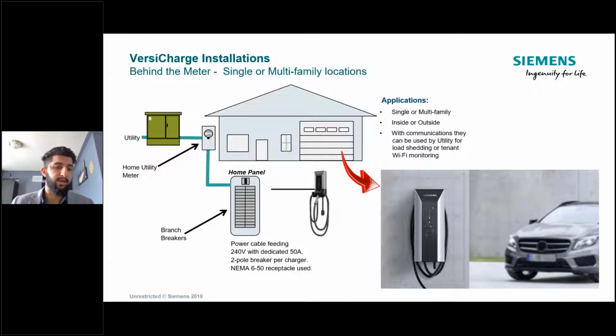You'd have a 2-pole breaker, 240 volts, with a dedicated 50 amp breaker for these chargers. Sometimes the utility would like separate metering for the charger in case there's any kind of subsidy being taken advantage of.